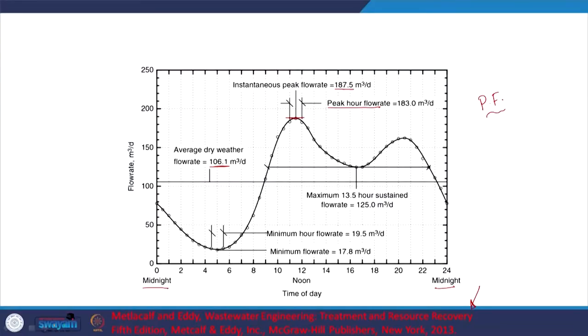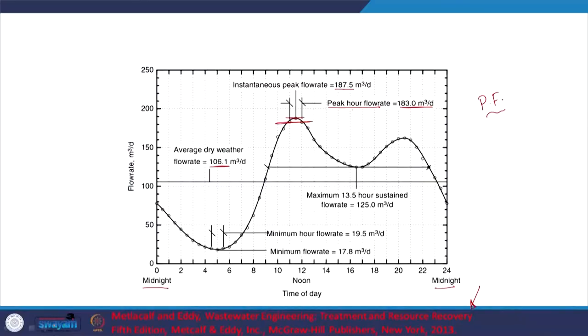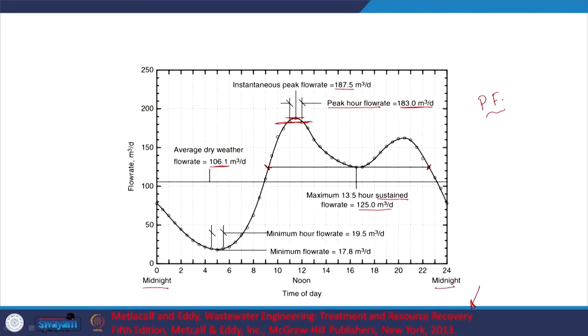The peak hour flow rate is 183 cubic meters per day. In developed countries, people typically look at the two-hour maximum; here we have the peak hour flow rate. That is the maximum flow rate sustained for a given period. For a 13.5-hour period, the sustained flow rate was 125 cubic meters per day. Obviously the peak flow rate is lesser when the time frame considered is greater. We also look at the absolute minimum flow rate and the minimum hourly flow rate.